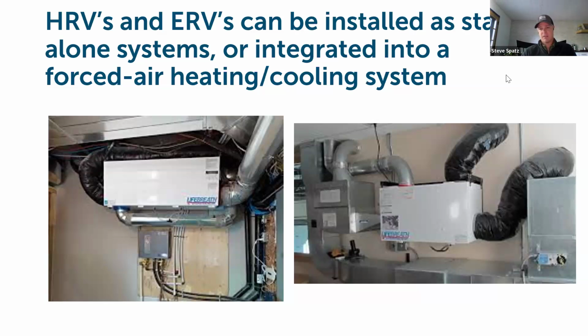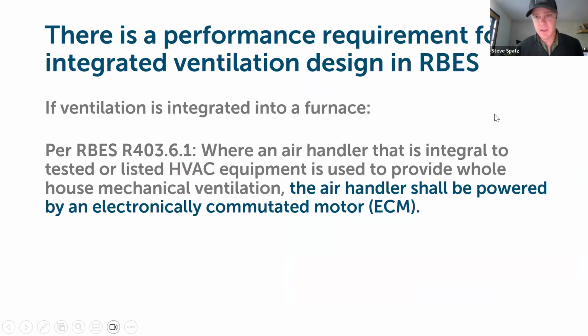If you are going to be combining the equipment, which is not an uncommon scenario, then you do need to be accounting for the fact that you're going to be relying on the air handler and the motor and the blower of the heating system furnace, essentially, to be moving your ventilation air more so than the blower and motor of the ERV or HRV itself. So you have to set up these systems with those pressure differentials taken into account, and the ability to control the ventilation side of the equation through the air handler of the furnace, so that you're getting ventilation air when the furnace is not coming on for a call for heat or cooling. The code also does require that if you are going to do this sort of combined duct system, the air handler motor itself for the furnace is an ECM motor.